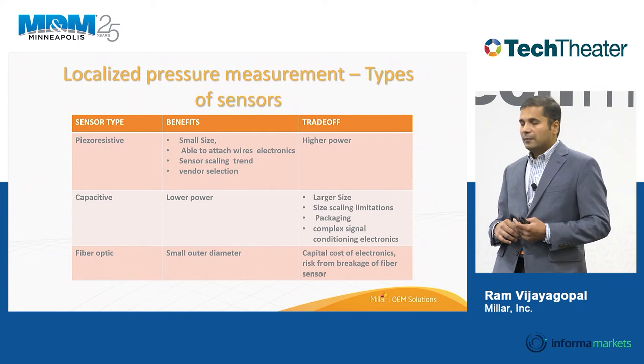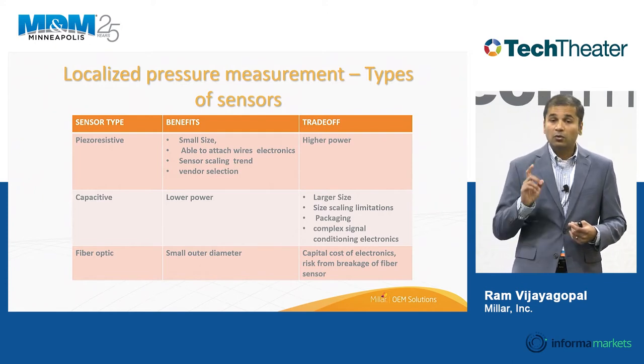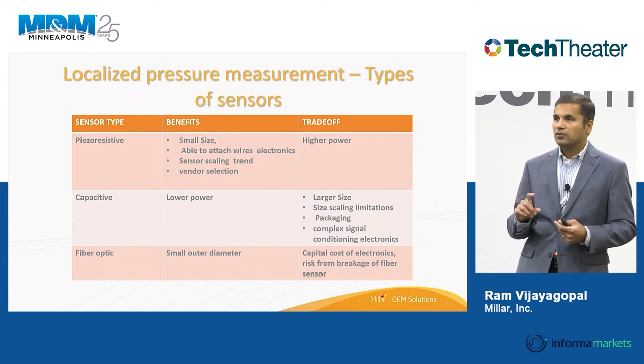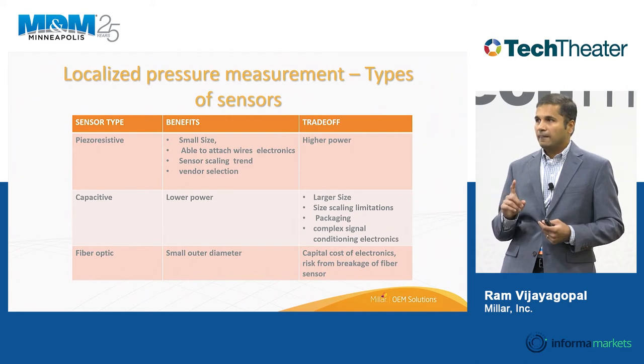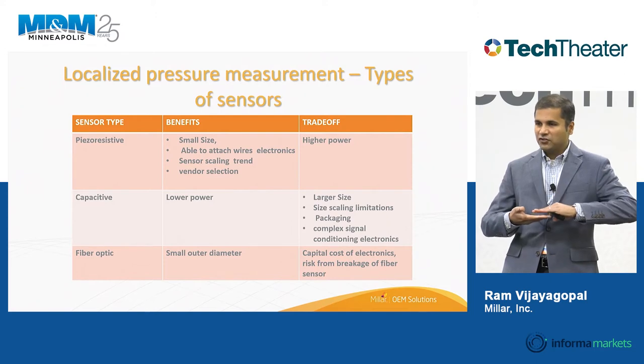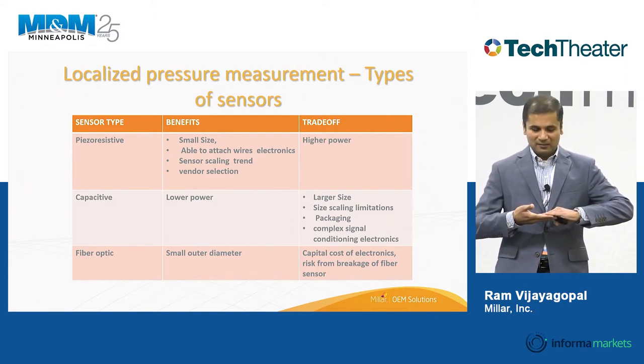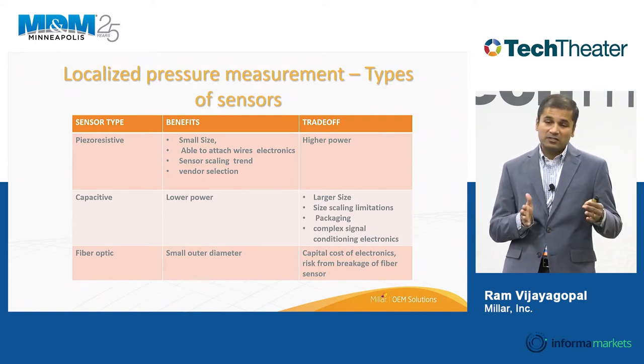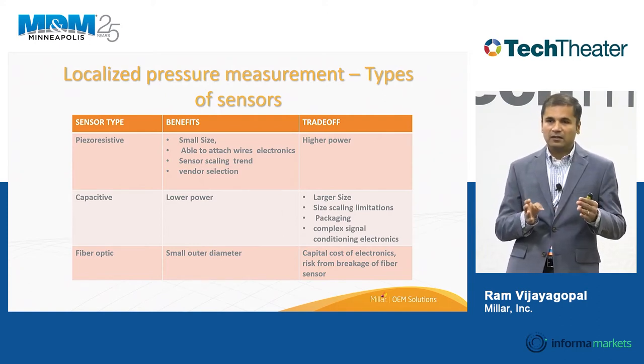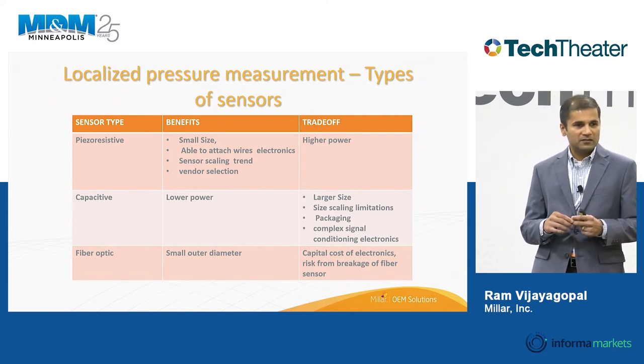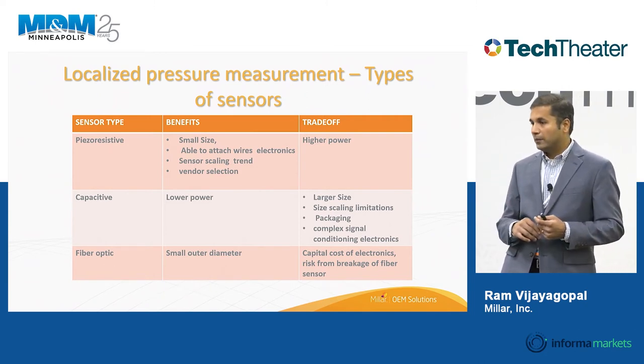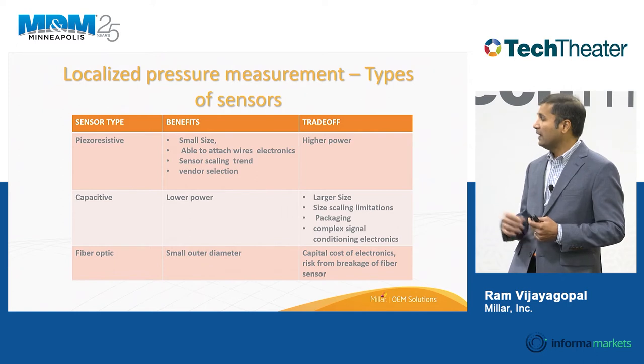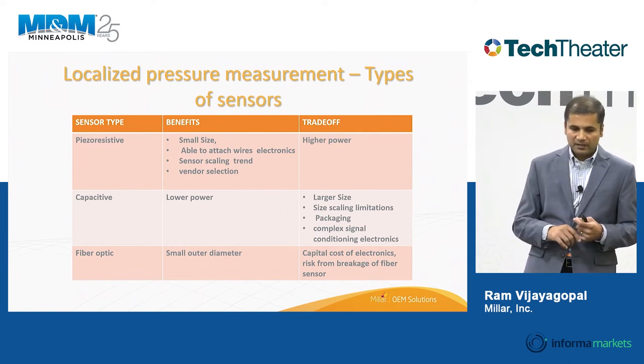Capacitive sensors are the second option. They're lower power and well-suited for implantable applications, but come with trade-offs: they must be packaged very closely to the signal-processing IC due to parasitics, they don't scale well and are typically much larger than piezo-resistive sensors, and they have complex signal conditioning electronics.